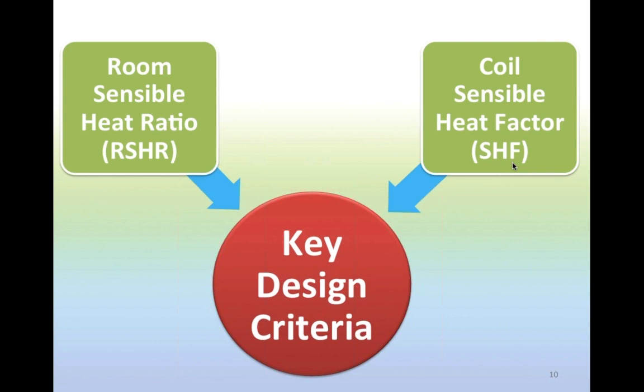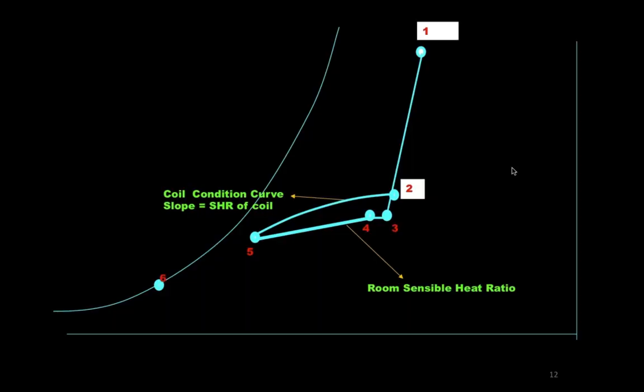Now, all of us know from fundamental design considerations and the psychrometrics that we are taught from early engineering curriculum that the coil sensible heat factor or the coil performance must be compatible with the room sensible heat ratio. In other words, it must suit the nature of loads in the room that need to be handled by the cooling coil. Let's look at it a little more closely in terms of how it happens in the entire system during its operation stage. When we select a cooling coil, we go through the whole process of finding out the total cooling load, how much of it is sensible and how much is latent, and then we select a coil designed for a certain chill water flow rate and a certain temperature difference across the supply and the return of the cooling coil, and we trust that the system will respond well at other conditions.